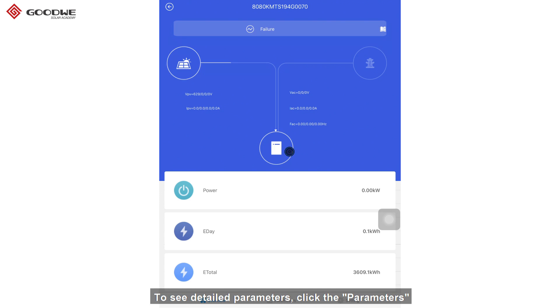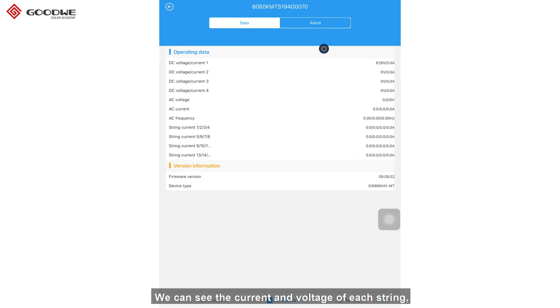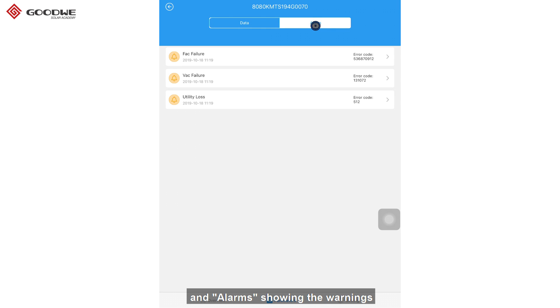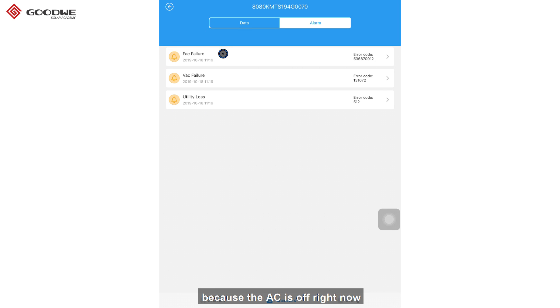To see detailed parameters, click the parameters. We can see the current and voltage of each string and alarms showing the warnings. Here, we have Vac failure, Fac failure and utility loss because the AC is off right now.